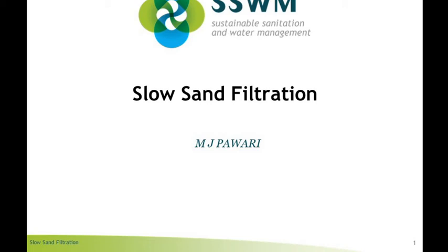The next important one is called the filter media of sand. Above the gravel, the layer of sand is placed, and the depth of the sand layer varies from 600 mm to 900 mm. Compared to the depth of the gravel, the depth of the sand is more because we require pure, clear filtration of water and the removal of all particles and solids from that water. So we keep the depth of the sand filter at 600 mm to 900 mm.